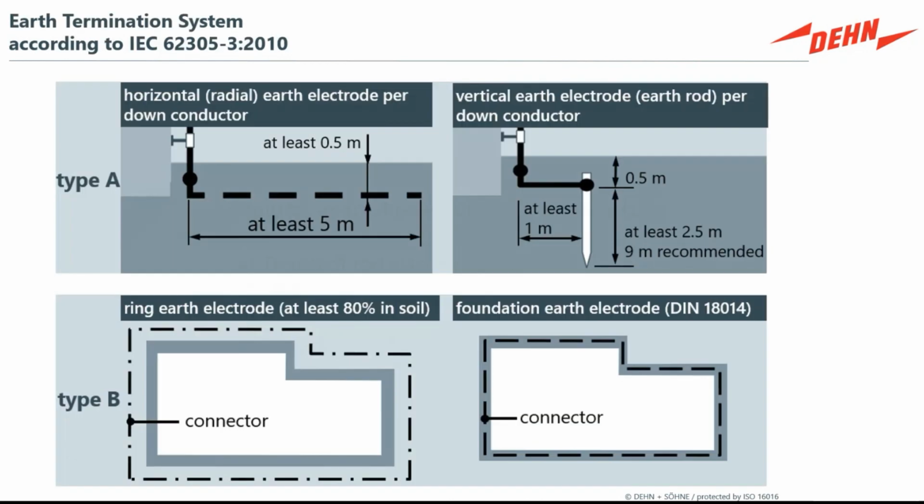And this is why you want to pay attention to the standards and install electrical grounding that meets the needs of lightning protection. If you only pay attention to the National Electric Code, Article 250, you will meet the National Electric Code. You can operate safe electrical power. That's great. And I always start with Article 250, except when you apply lightning protection, you need more. You need to pay attention to more attributes of grounding.